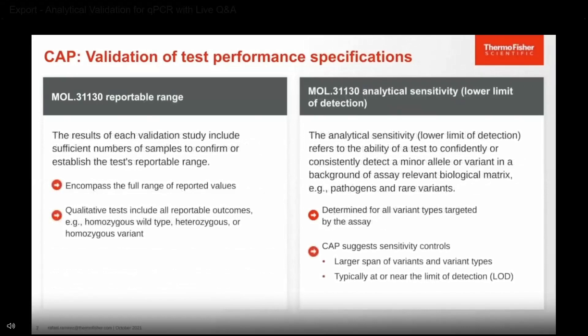In terms of reportable range, each validation study must include sufficient numbers of samples to confirm or establish the test reportable range. It's important to encompass the full range of reported values. In terms of pharmacogenetic studies, you need to make sure you cover all the potential reportable outcomes, such as homozygous wild type, heterozygous, or homozygous variant for all assays on your panel.